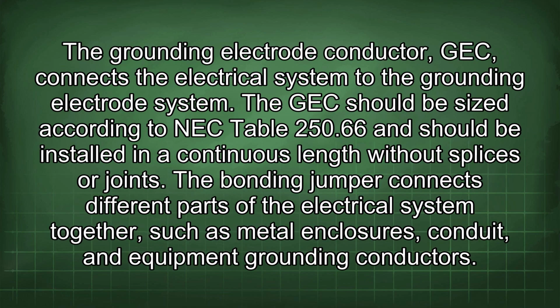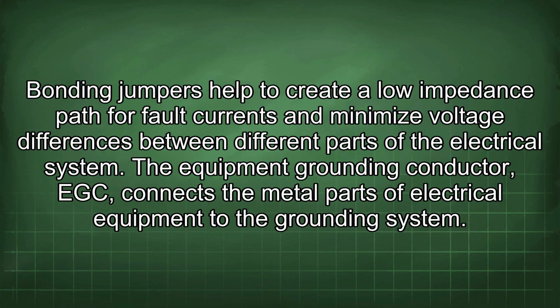The grounding electrode conductor (GEC) connects the electrical system to the grounding electrode system. The GEC should be sized according to NEC Table 250.66 and should be installed in a continuous length without splices or joints. The bonding jumper connects different parts of the electrical system together, such as metal enclosures, conduit, and equipment grounding conductors. Bonding jumpers help to create a low impedance path for fault currents and minimize voltage differences between different parts of the electrical system.